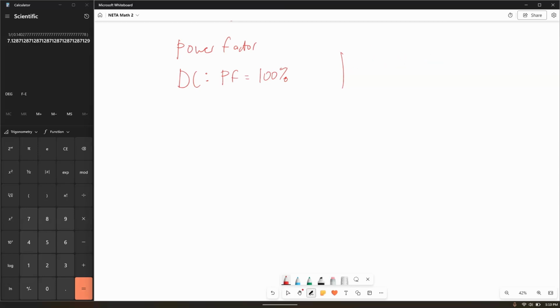The reason that we have power factor is because on an AC system, current and voltage can have a phase angle shift, a difference between these two points. Generally, we talk about power factor in a percentage, and it is a percentage of the true power over the apparent power. The units for true power are watts or kilowatts or megawatts or whatever, and the units for apparent power are VA.